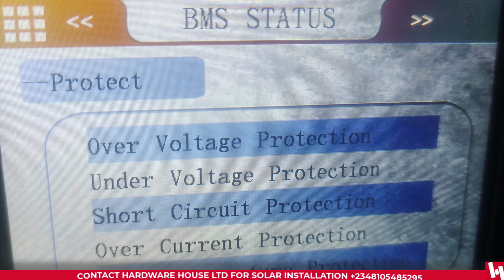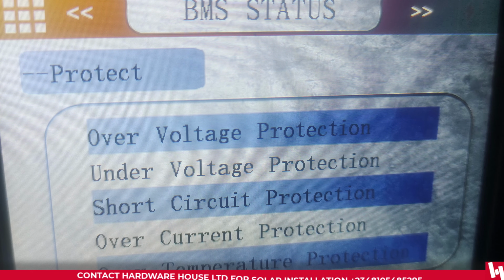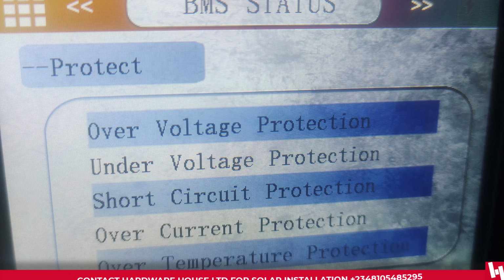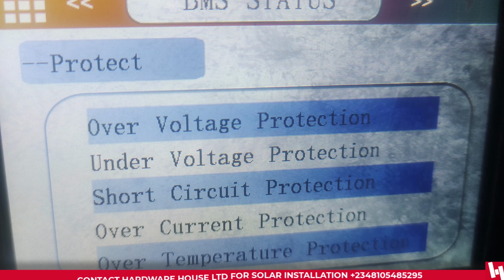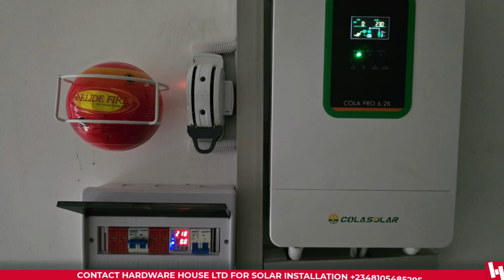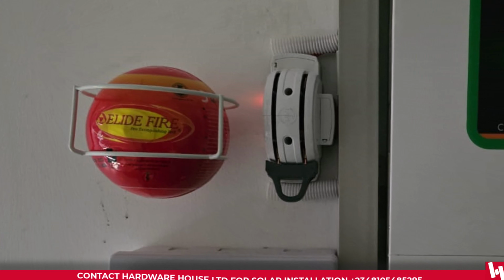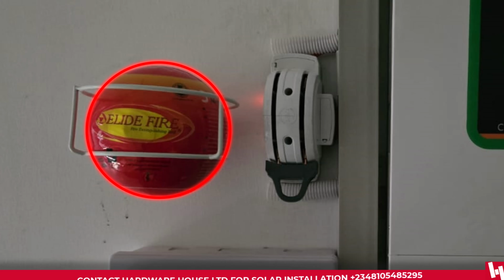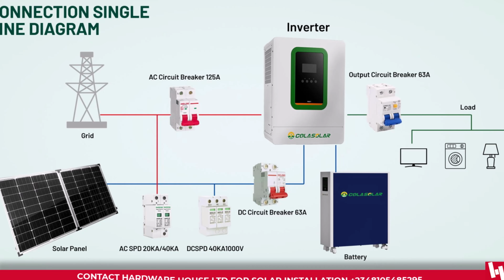We also have over temperature protection. So if the battery temperature gets too hot, probably due to overcurrents, which there is also a protection for, the battery will also shut down. So this is the third line of defense. And then we have a fourth line of defense. This one is when everything has failed. The surge protectors, which is the first line of defense, probably somehow failed to flip for some reason. The power management system on the inverter somehow fails to interact with the battery management system, or somehow fails to defend the battery and the load from any form of surge or short circuit or overload situation.